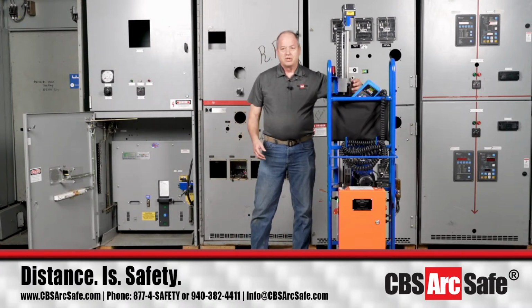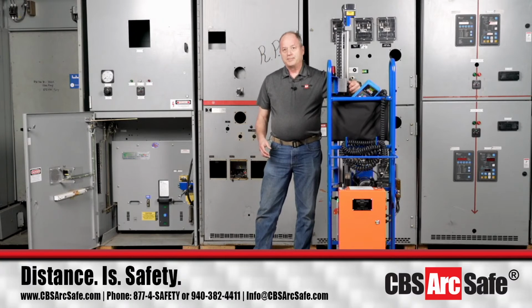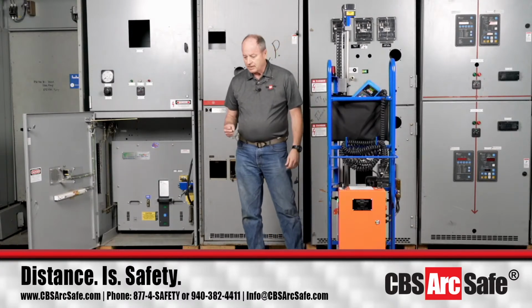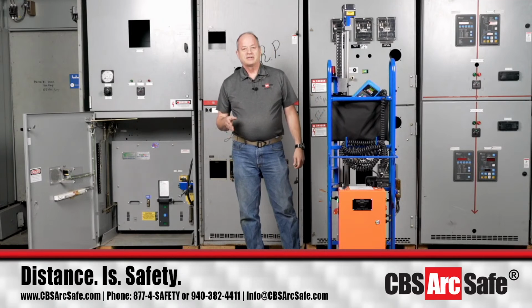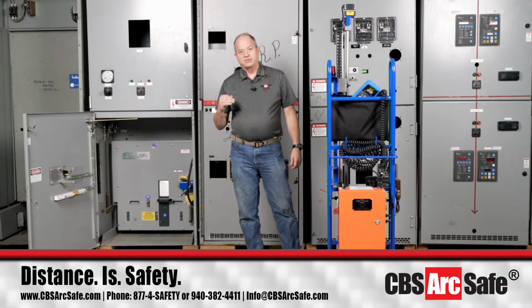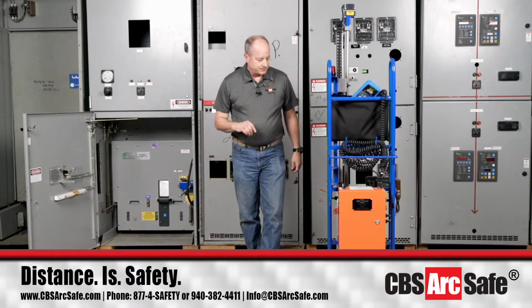And that's one of the things that you need to understand: you have to work to look at the condition of your switchgear. Remote racking doesn't fix your problems, it helps you identify the problems, it helps to keep your people safe. So when you're working with a breaker like this, as long as it operates normally, when you get to the end of the racking mechanism, that's great. But if you have to back it off a little bit, don't be surprised if you've got one in there that's been there for a long time, and that's what you have to do.